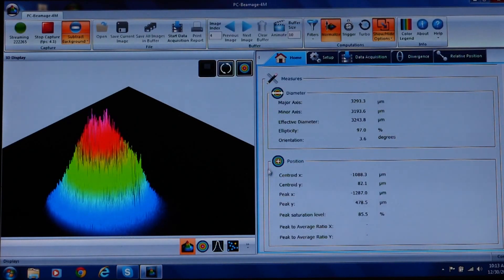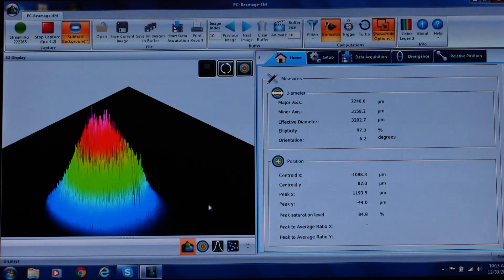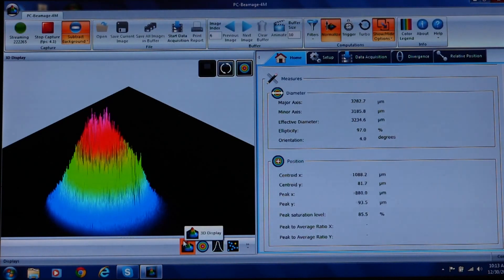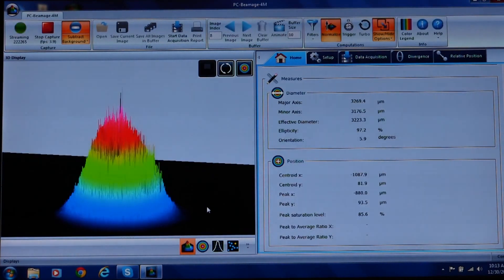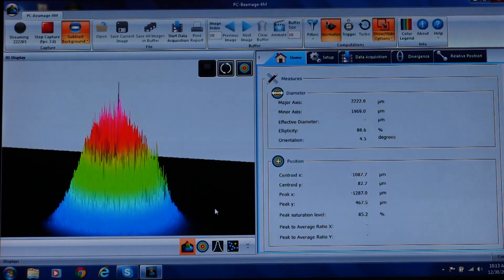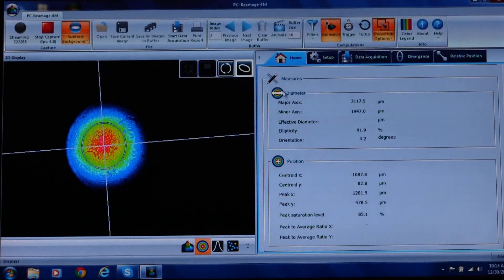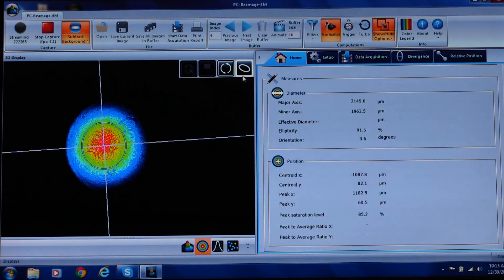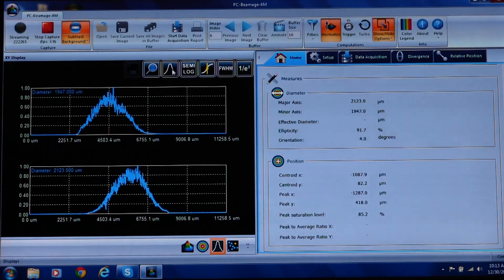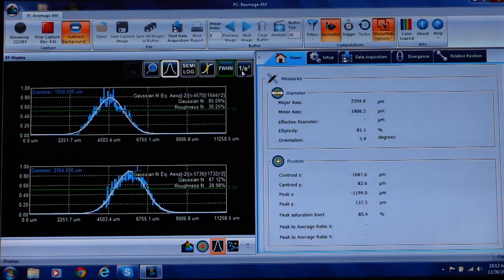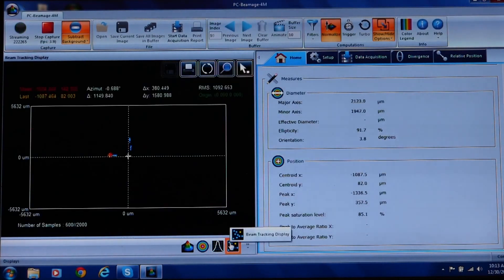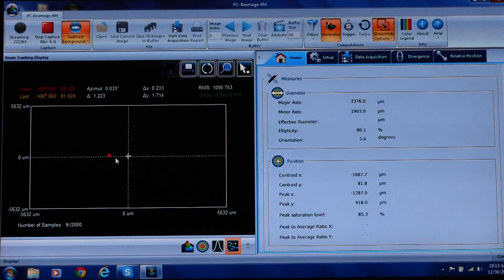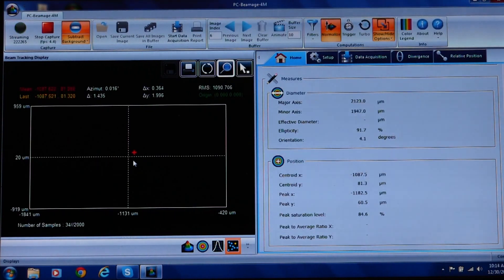Though this is not a detailed demonstration video, we'd like to take a few more minutes to show you the four graphic displays. We are now looking at a 3D color display of the beam profile which you can manipulate or zoom in on using your PC mouse or pad. Next, we'll move to the 2D display where you can add an ellipsoid. Then, we'll select the XY plot and add a best fit Gaussian curve, a full width half max, and one over E squared lines. And finally, we'll move to the beam tracking display. Here, you can observe the movement of a laser beam centroid with micron resolution. This is great for tracking the beam stability or beam steering over time and temperature.